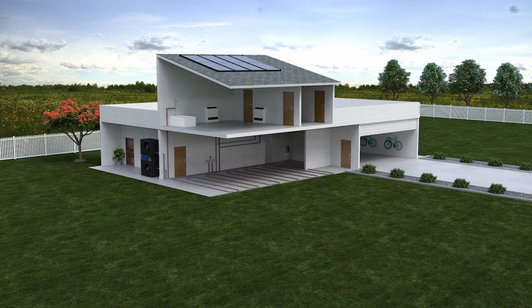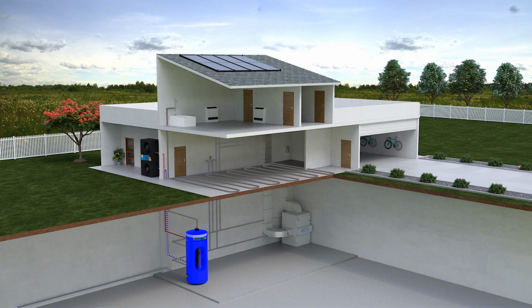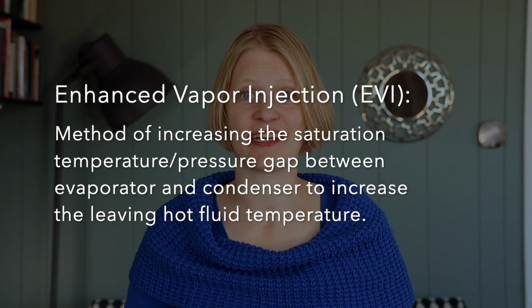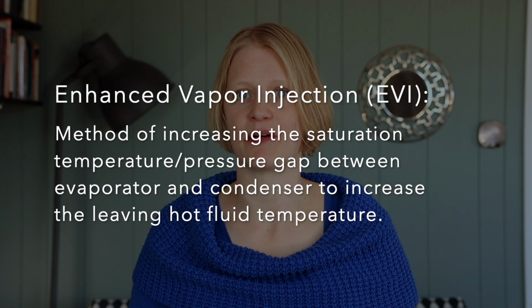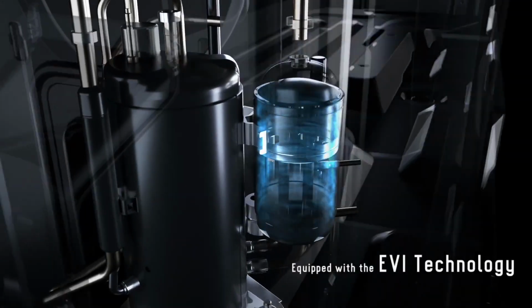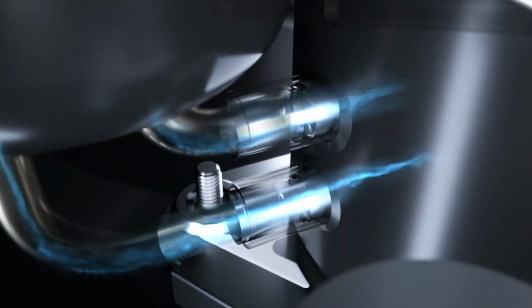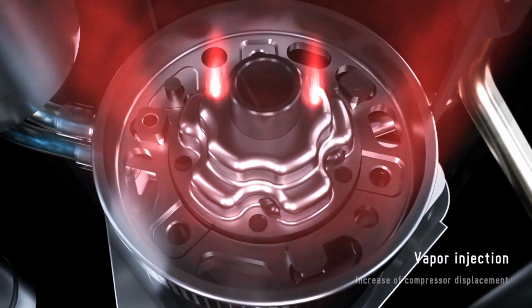Hydronic heat pumps can therefore be fixed speed or two-speed. Variable speed like EVI is making its way into hydronic heat pumps now, in part because fixed speed or two-speed compressors are going away and EVI compressors are becoming less expensive. Also because EVI is sexy, but the efficiency gain is limited compared to forced air.